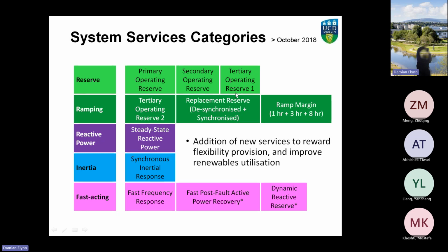A question that was being asked earlier was what happens whenever there is a fault, and should you prioritize your active power recovery or your reactive power recovery? Most power systems around the world prioritize reactive power recovery, but this particular system service actually emphasizes active power recovery, so it's unusual. That's because there's so much wind in the Irish system potentially, and it could be quite concentrated.